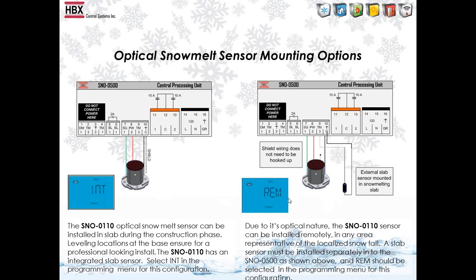If you're remote mounting the optical sensor, or if you're using it in a paving stone application, you would make sure that you set the slab sensor to REM, which is remote. So what this does is you now don't need the white wire from the optical sensor, and you don't have to hook the shield up, but your external slab sensor would get hooked up in these locations. So 9 and 10 would be where you hook up your external sensor.